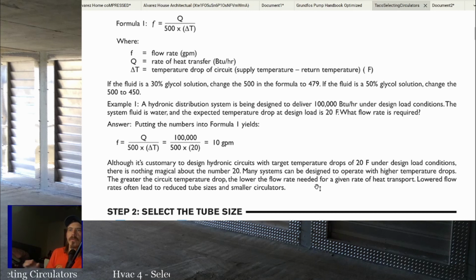And this is kind of why, depending on the system, guys can get away with just, say, there's a B&G pump in there with these performance characteristics, and you switched it out for a Taco 007, which is a pretty common pump, right? So the reason they get away with that, even though they didn't make sure that the pump curves were the same, is they basically just changed the temperature drop in the system. Unfortunately, you're not always going to get that lucky.